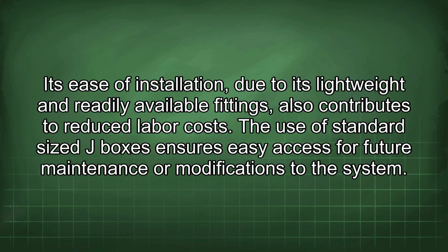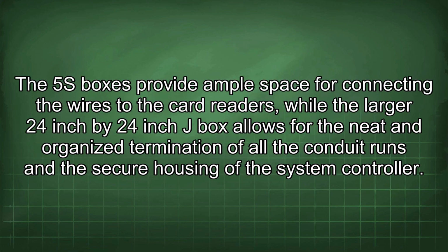The use of standard-sized J-boxes ensures easy access for future maintenance or modifications to the system. The 5S boxes provide ample space for connecting the wires to the card readers, while the larger 24-inch by 24-inch J-box allows for the neat and organized termination of all the conduit runs and the secure housing of the system controller.